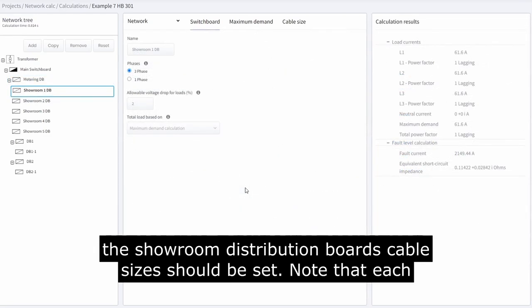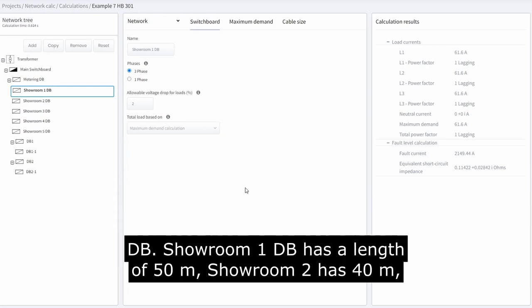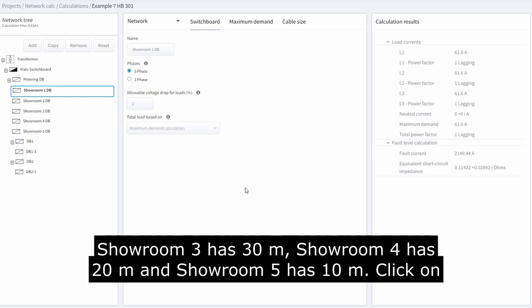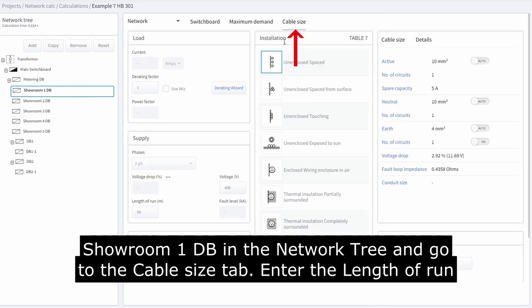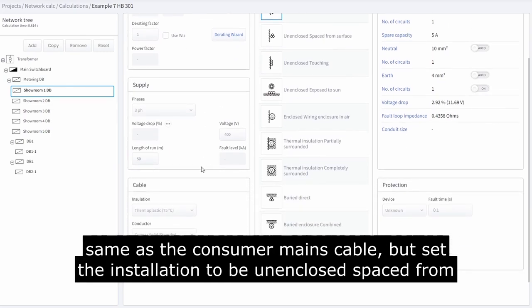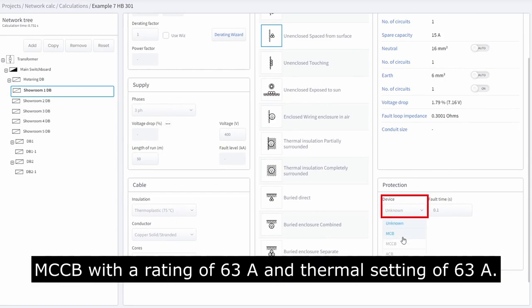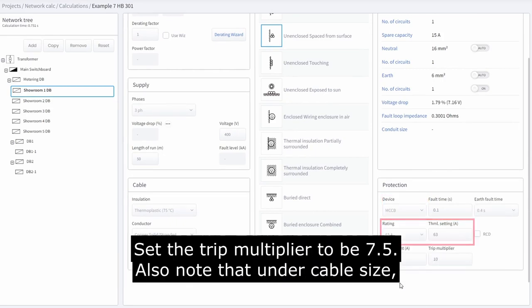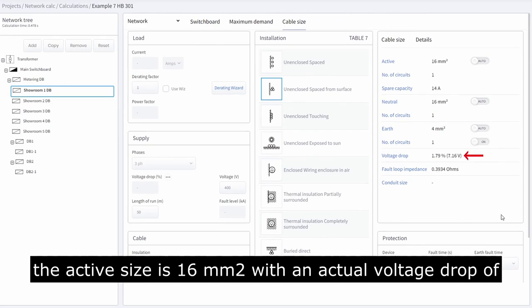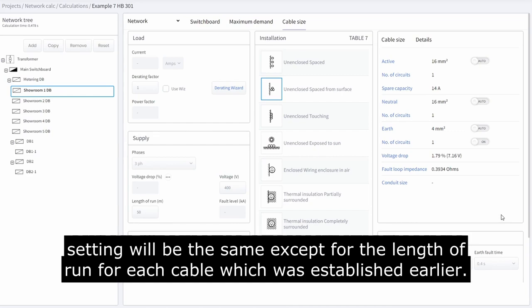Next, the showroom distribution boards' cable sizes should be set. Note that each showroom DB will have a different cable length depending on its position relative to the metering DB: showroom 1 is 50 meters, showroom 2 is 40 meters, showroom 3 is 30 meters, showroom 4 is 20 meters, and showroom 5 is 10 meters. Click on showroom 1 in the network tree and go to the cable size tab. Enter the length of run as 50 meters. The cable type is the same as the consumer mains cable, but set the installation to unenclosed spaced from surface. Under protection, set the device to MCCB with a rating of 63 amps and thermal setting of 63 amps, and set the trip multiplier to 7.5. The active size is 16 mm² with an actual voltage drop of 1.79%. Do the same for showrooms 2 to 5 — every setting will be the same except for the length of run.